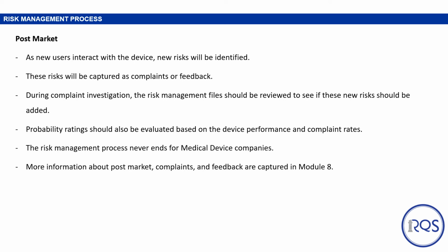Now let's briefly touch on post-market. As new users interact with the device, new risks will be identified. These risks can be captured as complaints or feedback. During a complaint investigation, the risk management file should be reviewed to see if these new risks should be added. Probability ratings should also be evaluated based on device performance and complaint rates. And the risk management process ultimately never ends for medical device companies. All throughout post-market, all throughout the device's life cycle, risk management will be in play. But more information on post-market complaints and feedback will be captured in Module 8.